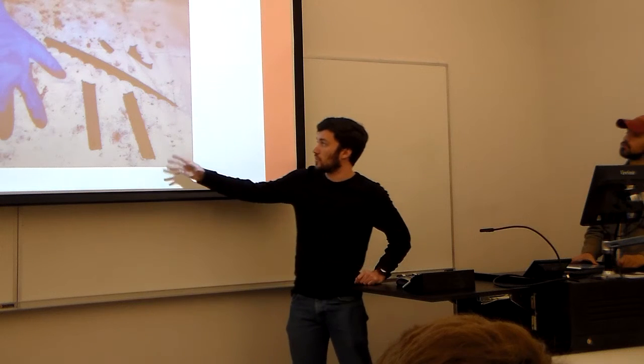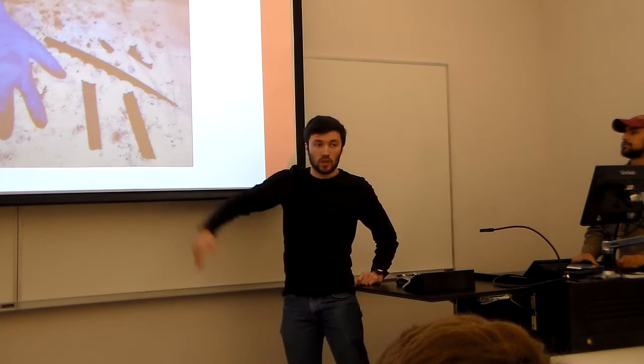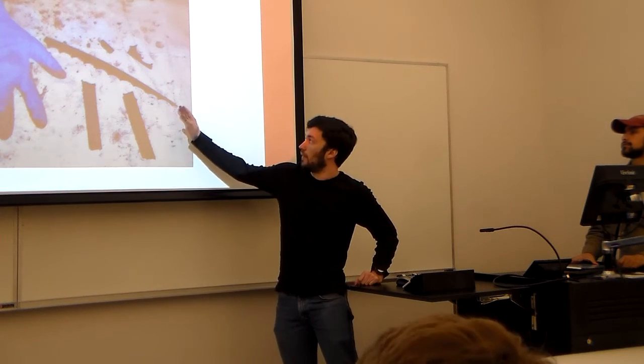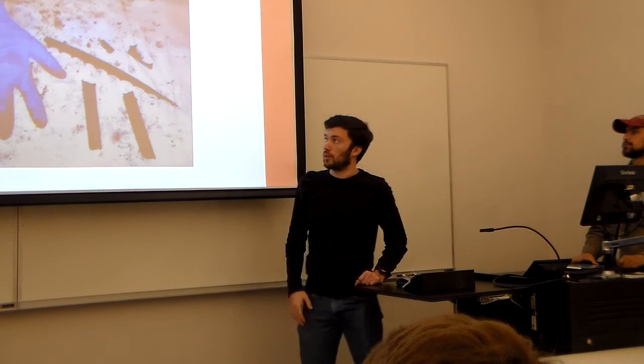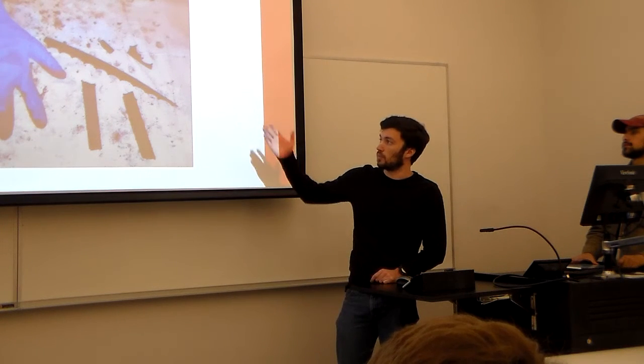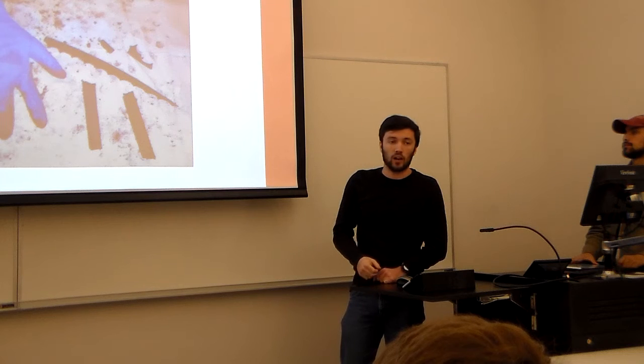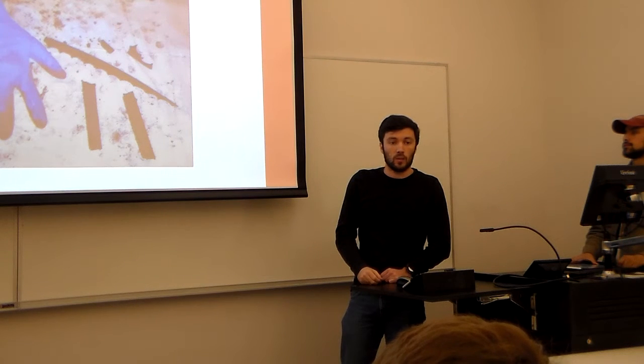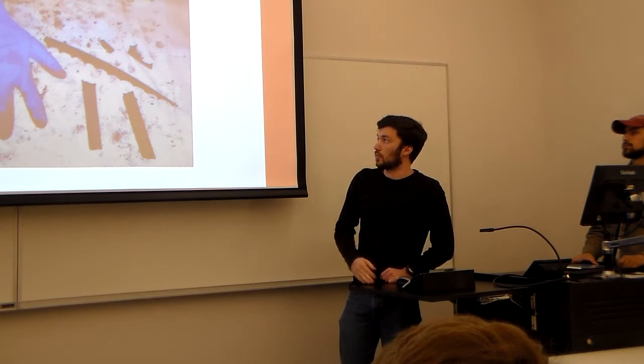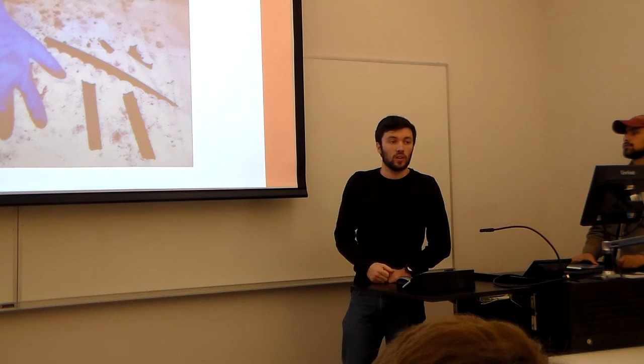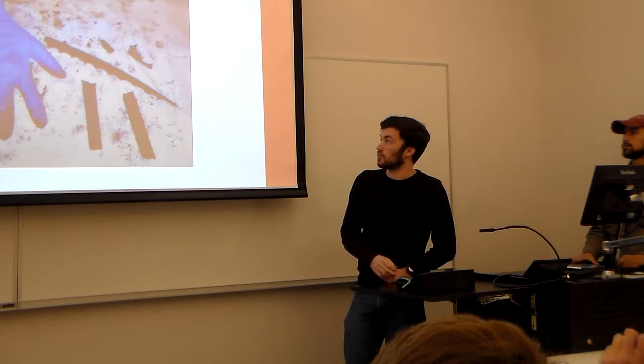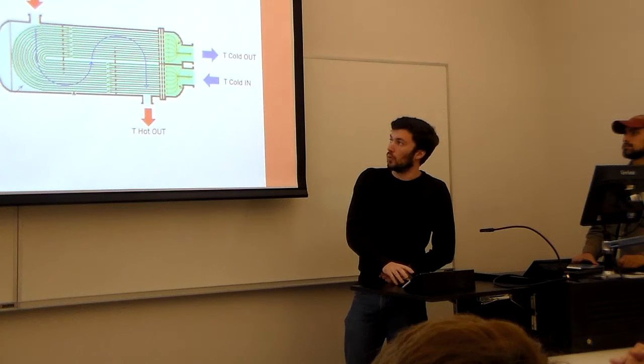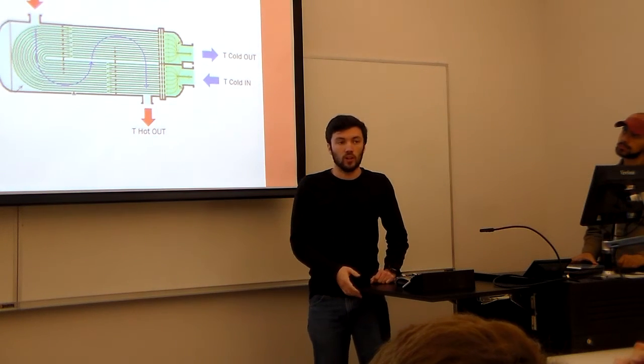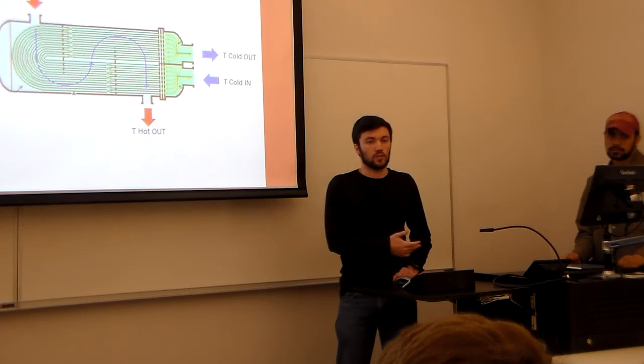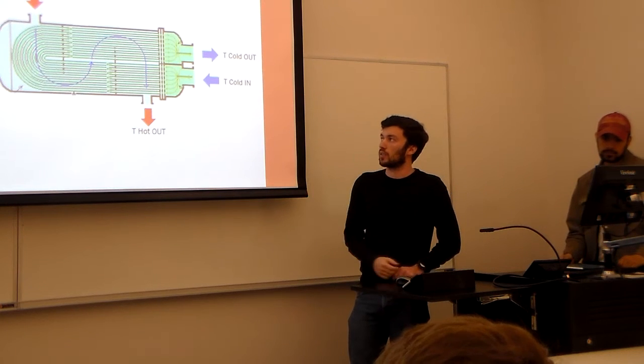So you can actually see that these are two tubes that have completely been severed off inside the heat exchanger, and that is actually the edge of one of those baffle plates. And that was my teammate's hand there, just to give you an idea of how large these pieces really were. I was told by other people that these were actually significantly larger than most debris that is found in these situations. So you might be wondering, how in the world did they know that there was an issue other than these sensors saying there's debris? How do they know it was this?